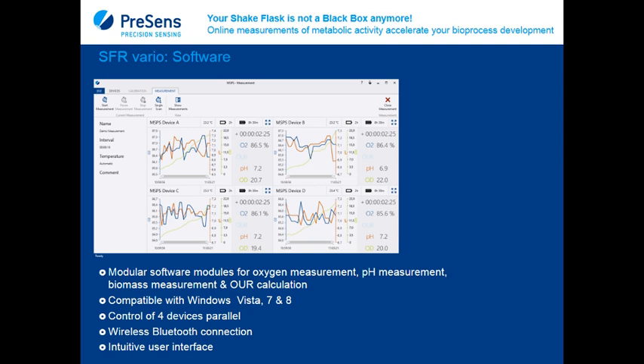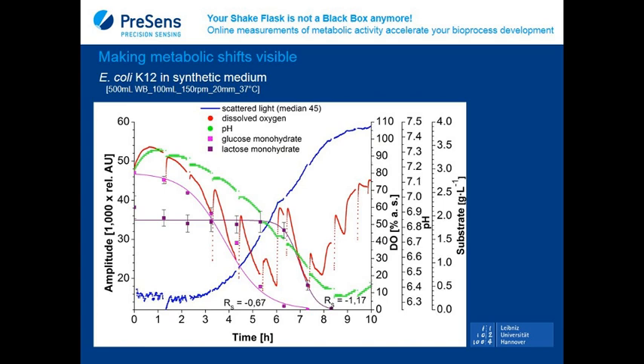Before we come to all these questions, we have a look at some examples of how this system is applied. A very interesting application of the sensor is monitoring of metabolic shifts. So first, let's have a look at what is shown on this graph here. We have 3 online measured parameters: scattered light, dissolved oxygen, and pH, and 2 offline measured concentrations of glucose and lactose. You see here that the online measurement shows some gaps. This is caused by stopping the shake flask due to the offline measurement of glucose and lactose.